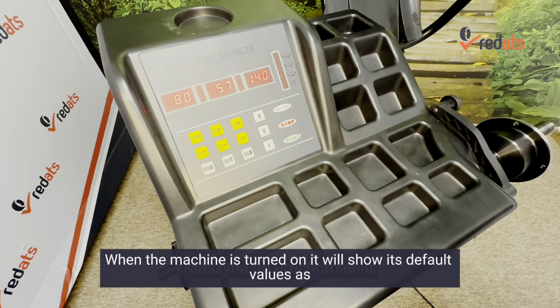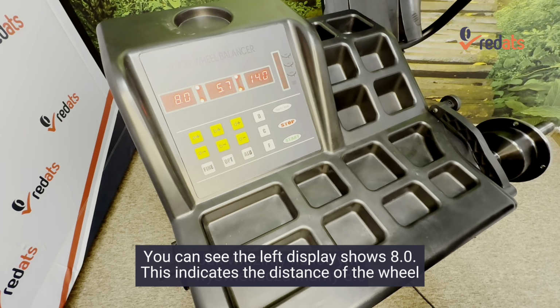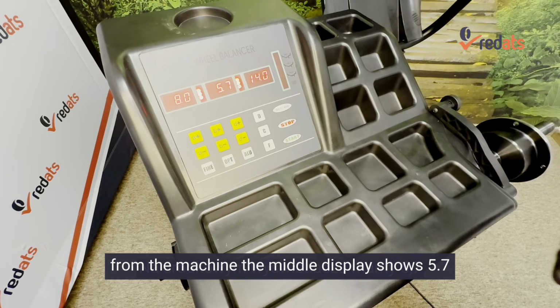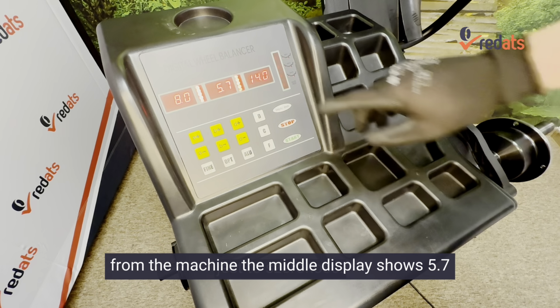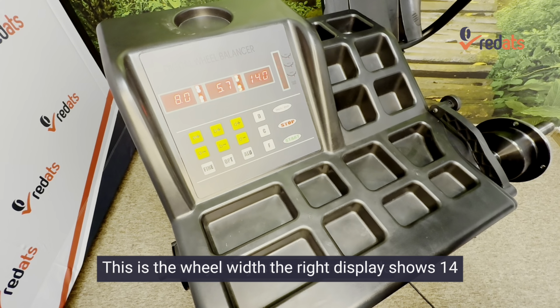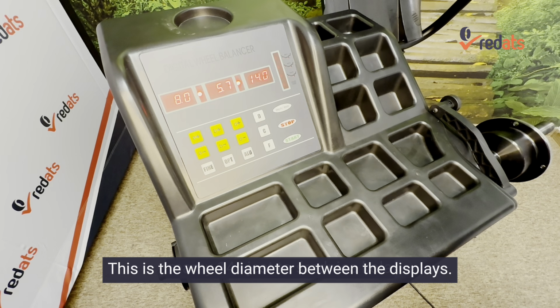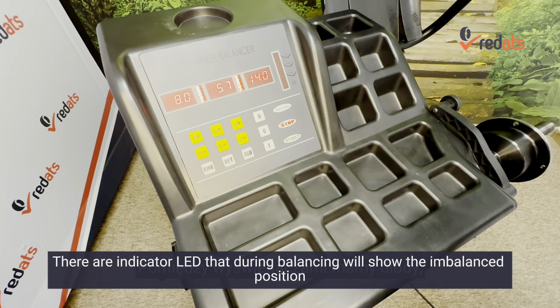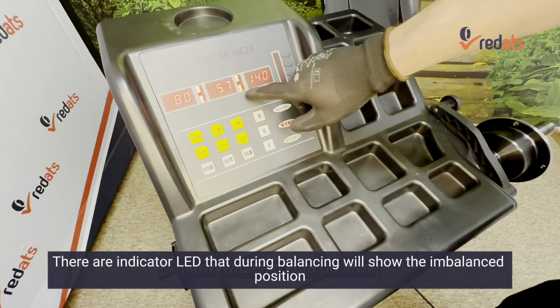When the machine is turned on, it will show its default values. As you can see, the left display shows 8.0. This indicates the distance of the wheel from the machine. The middle display shows 5.7. This is the wheel width. The right display shows 14. This is the wheel diameter.